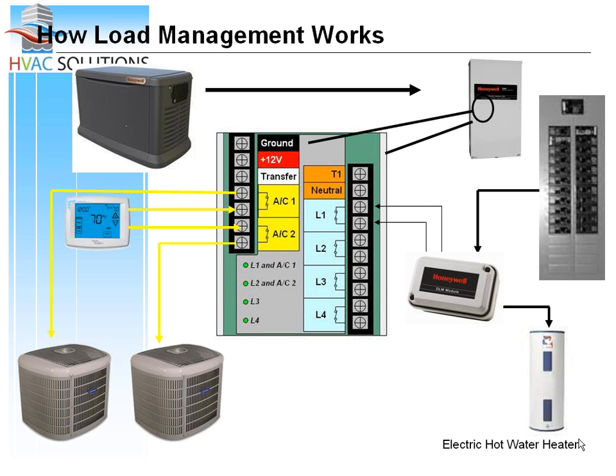So if I was to run through this one more time, and only because this is a very important part of this presentation: if we lose power, utility goes out, the generator kicks on, the first thing we do, we send power to the 115s in the customer circuit breaker panel. Once we have power there, we look at AC1 and L1. And if we can start them, we do. Then it goes to AC2 and L2. Then on to L3 and L4.